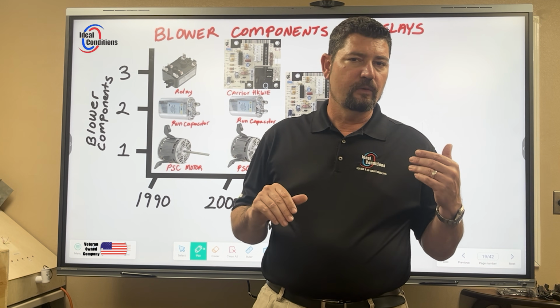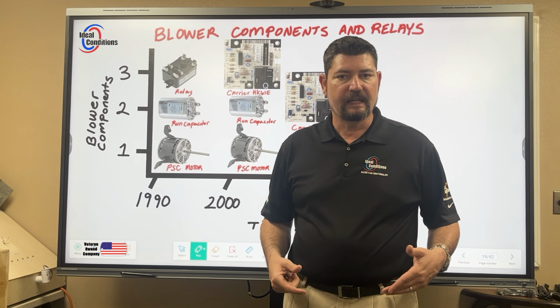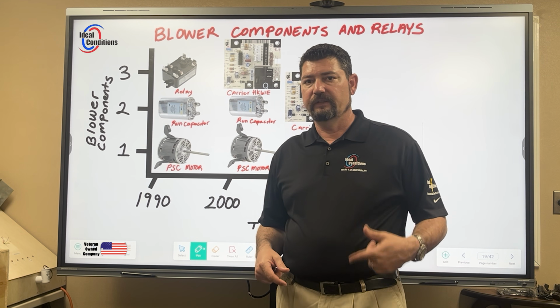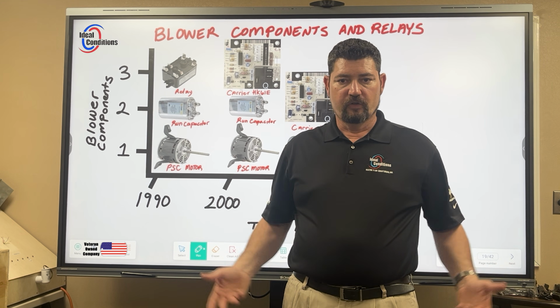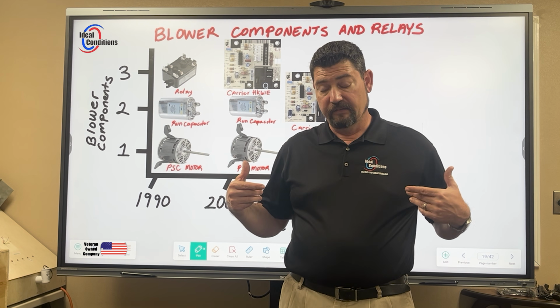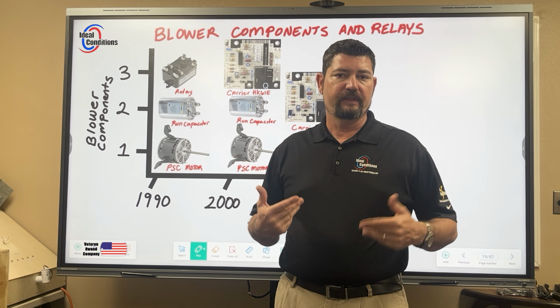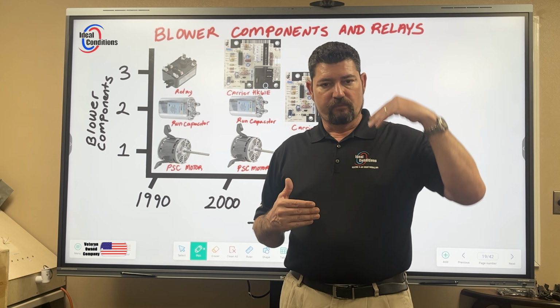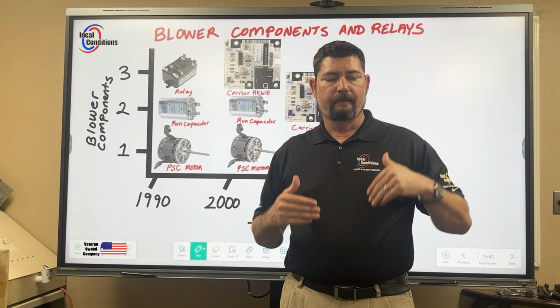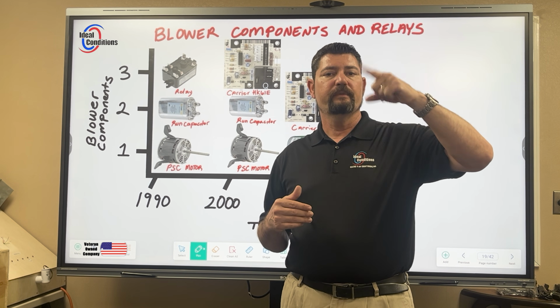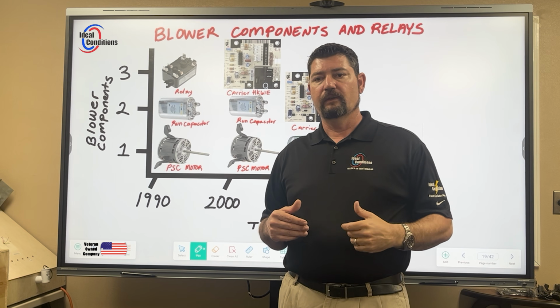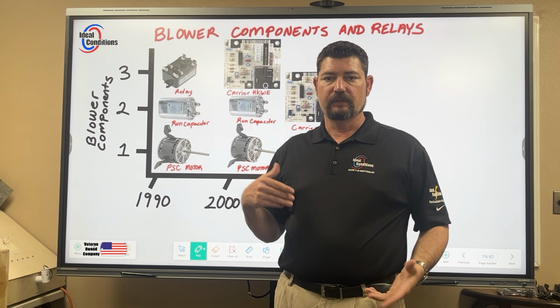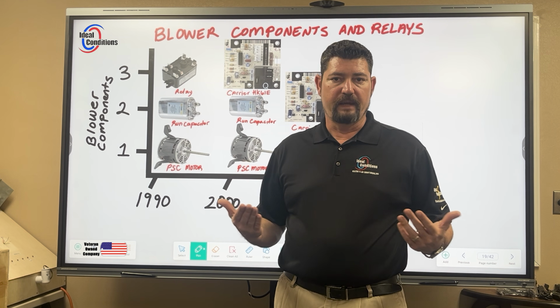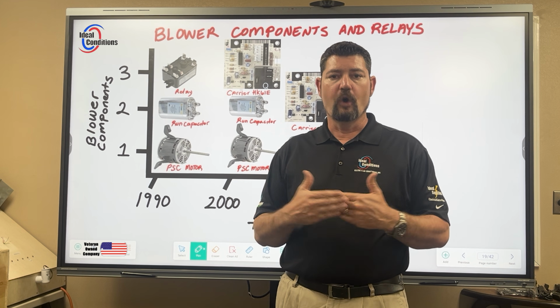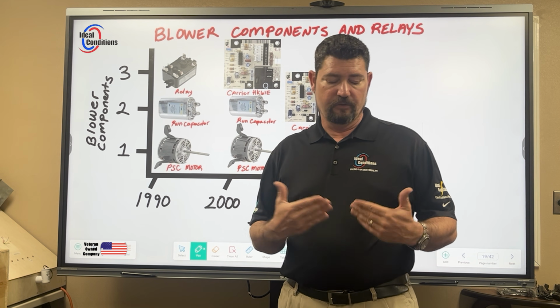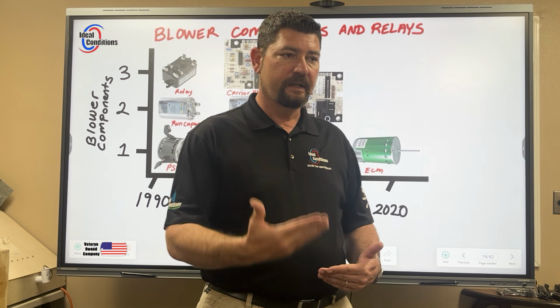But if I want to wire to a medium low speed and get a little bit more dehumidification out of the coil, a little bit more heating capacity out of the coil as I'm moving heat across it, or as I am dispersing the heat off that coil, then if I'm running heat strips in addition to that, I want to make sure that I pick up a little bit more CFMs so I don't have issues with limit switches going bad because they're opening because the plenum temperature is too high. So they want you to pick up those speeds.